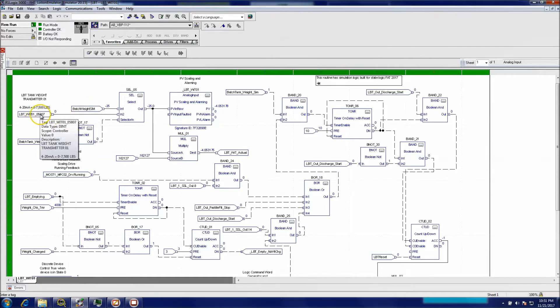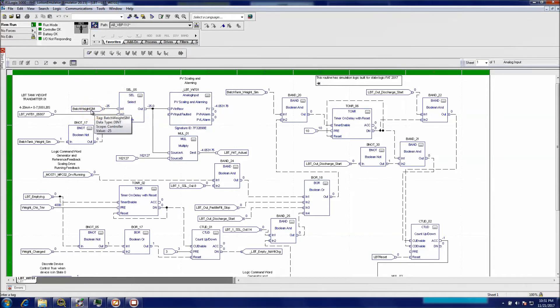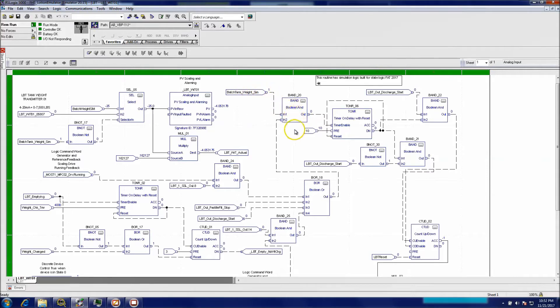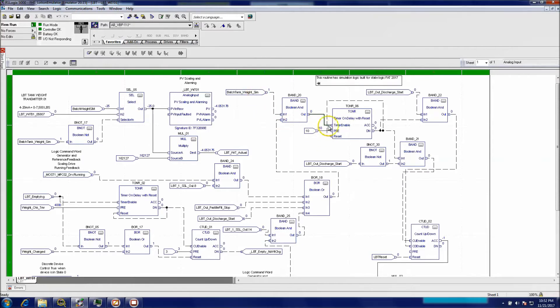Normally you would just have the weight coming in to the analog input and it would output the tank weight. What I've done is added a tank simulation — a batch simulation — inside of this instead. If the simulation is on, then I want to use a selector, which is basically the batch weight again. Using that batch tank weight 'simulate on,' if this is okay and one of these situations is good, and the batch simulation is on, then I want to start the counter.